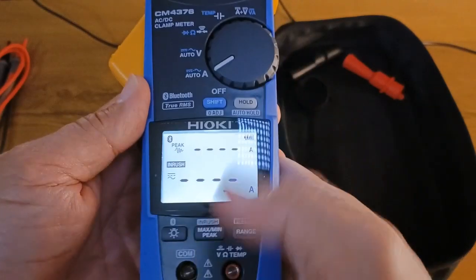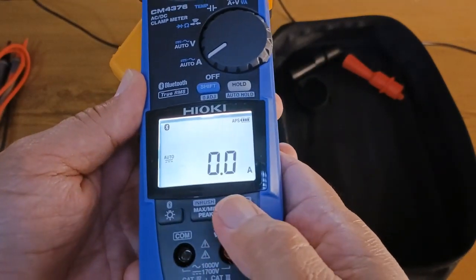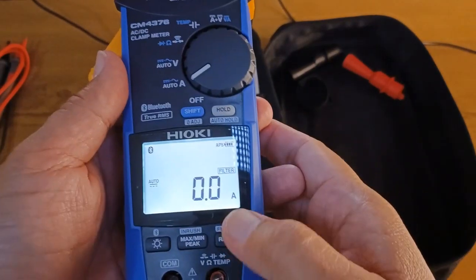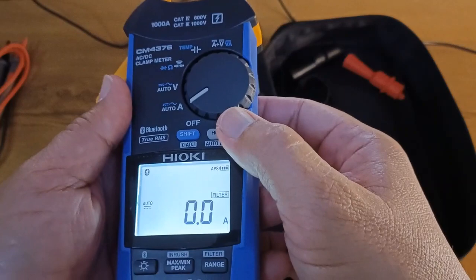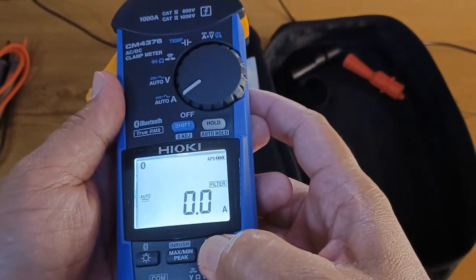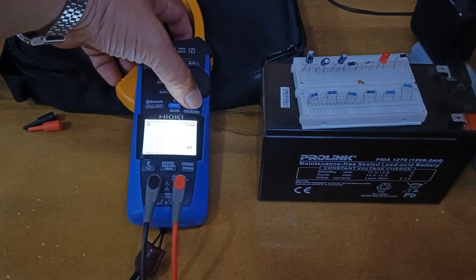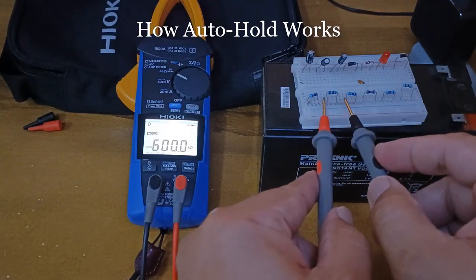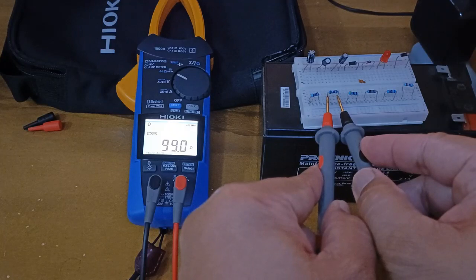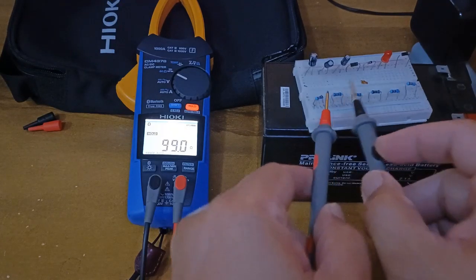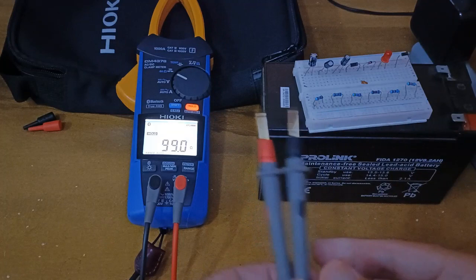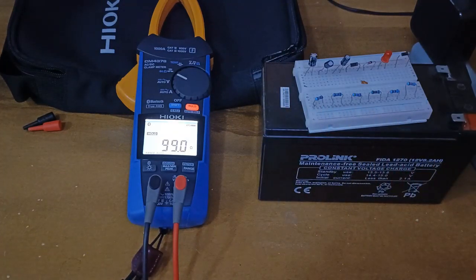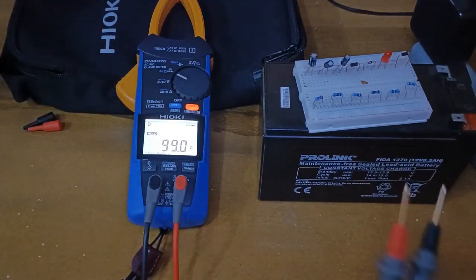It also has a filter function, which filters out unnecessary frequencies, so you get accurate results. The 4376 is equipped with the normal hold button and the auto hold button. By long pressing this hold button, I will engage the auto hold function. Once the parameter stabilizes, I can remove the test leads from the test points and the value will be retained on the screen. So this makes the auto hold function very convenient.